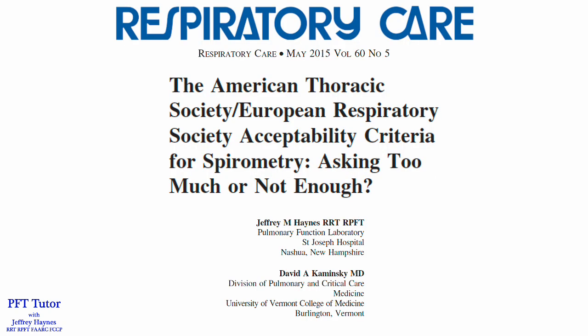If you're using spirometry software based on the 2005 ATS-ERS standards, you may see this pattern without an error message from the software because it wasn't designated as an error until the 2019 standards were published. In 2015, Dr. Kaminsky and myself wrote this letter in Respiratory Care supporting the idea that submaximal inhalation should be flagged as an error during spirometry testing.